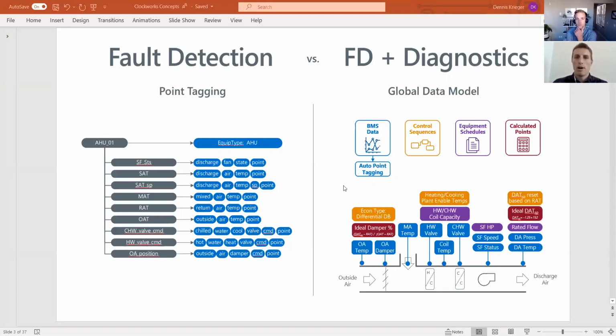But what's often overlooked is this idea that we need to go beyond simple point tagging. If you're tagging points without any objective behind it, there's really no purpose, right? Like, why am I tagging this point as a discharge fan state, for example? To get beyond that, we need to get into an actual data model or a data ontology. This is, to me, one of the first and frankly one of the biggest differentiators between a simple rules-based fault detection analytics platform and true fault detection and diagnostics.